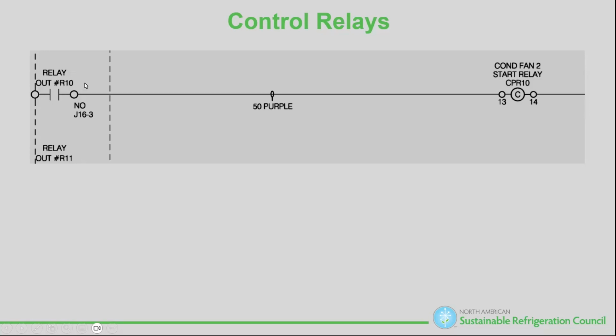So when this controller - this is a Carel controller, a Form A contact - says okay, I need the condenser fan, he's going to close this relay. That happens at the controller in the logic, we're going to talk about that a little later. Close that, simply means I'm going to close that, I'm going to energize this. That means for this to be energized, I should have voltage here and here, 208, right?